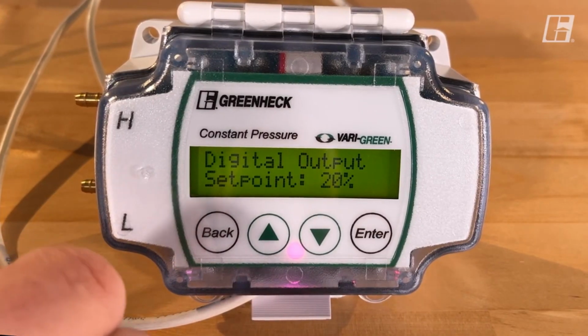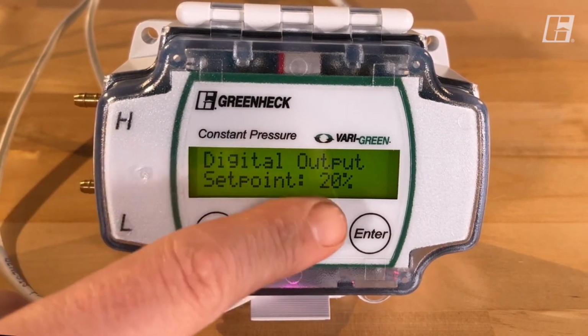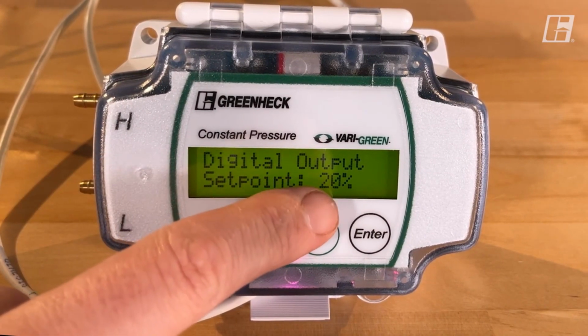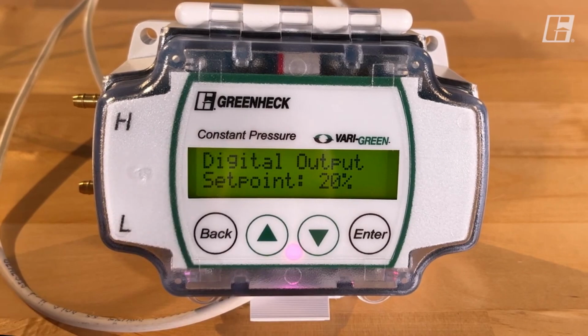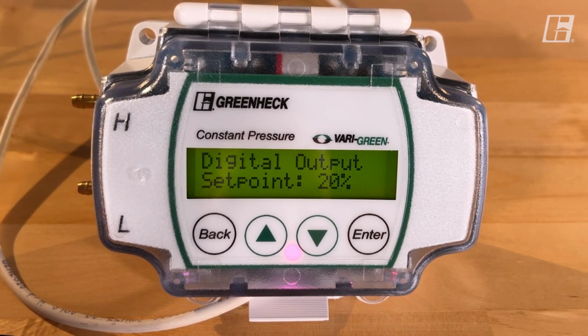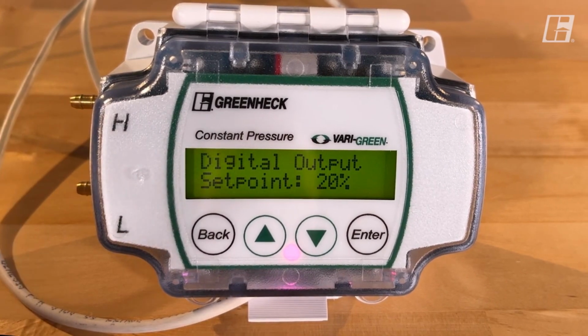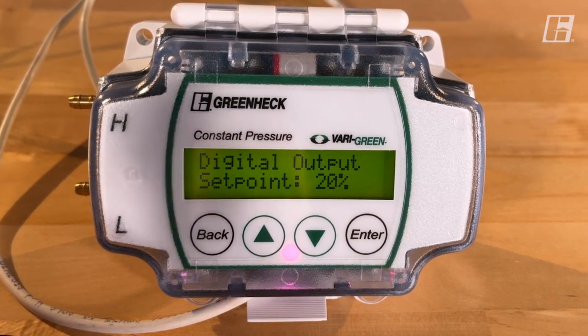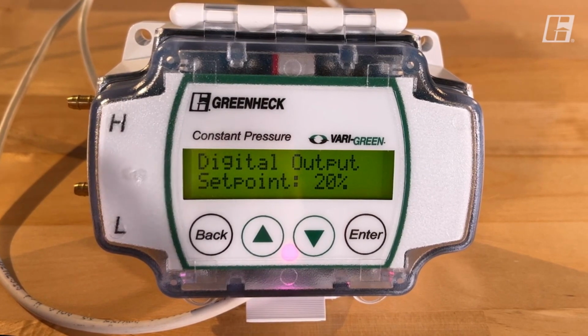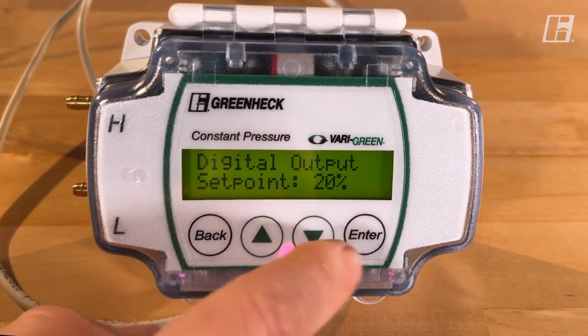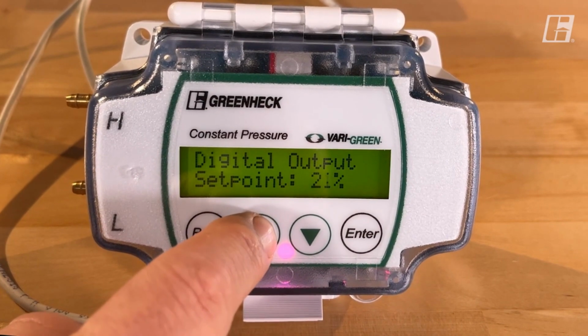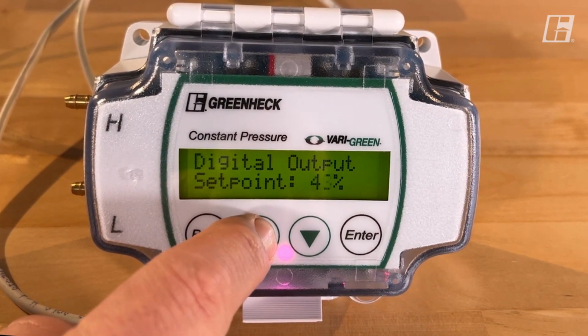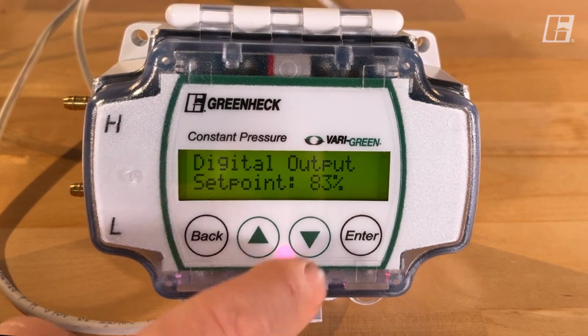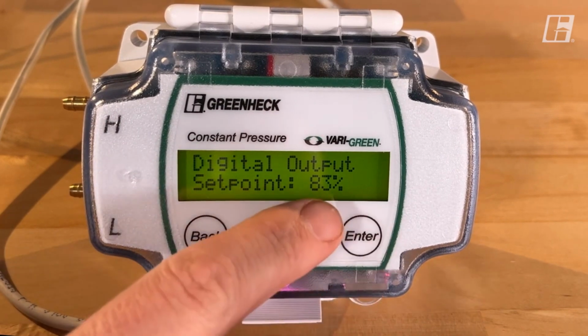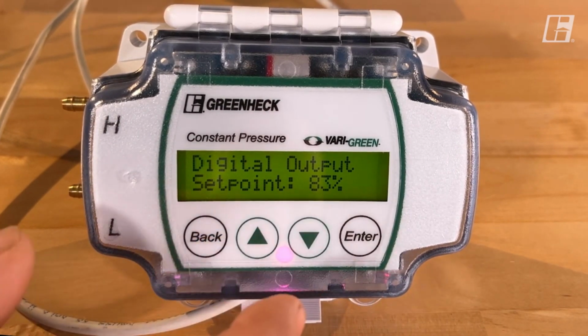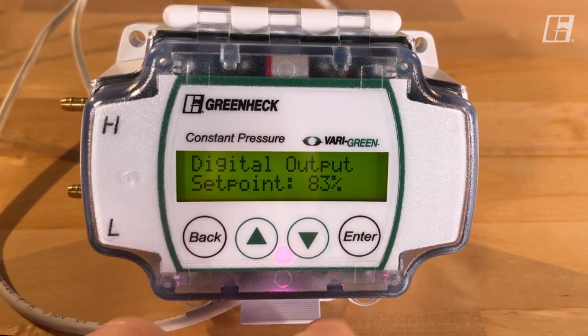Digital output set point. This is that set point. When the motor hits this percentage or greater, the digital terminal on the inside of this will actually close. Again, that was for reference. Other controllers or their building management system could see, hey, the motor is at, we'll say 70% or whatnot. So now when the fan is speeding up, if we hit 83%, that digital terminal will close.